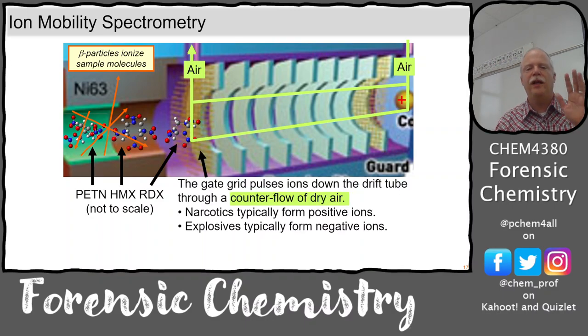This grid plate pulses the ions down the drift tube through a counterflow of air. Narcotics typically form positive ions, so the detector needs to be negative for narcotics, and they'll go down and hit it. But if you're looking for narcotics, you're blind to explosives. Explosives form negative ions, so you make the detector positive so the explosives go down and hit it, but then you're blind to narcotics.